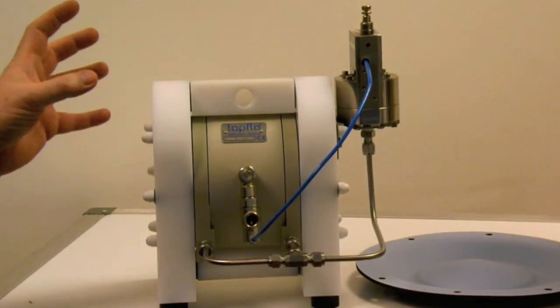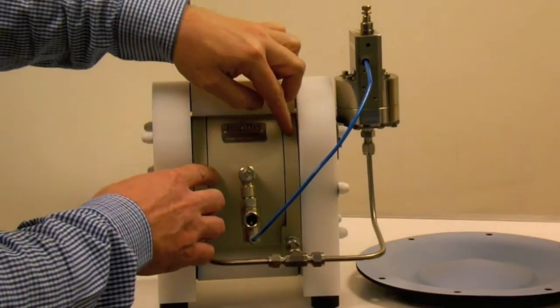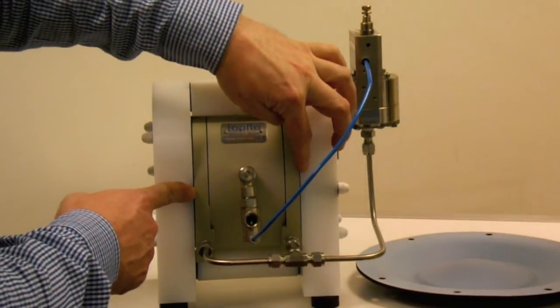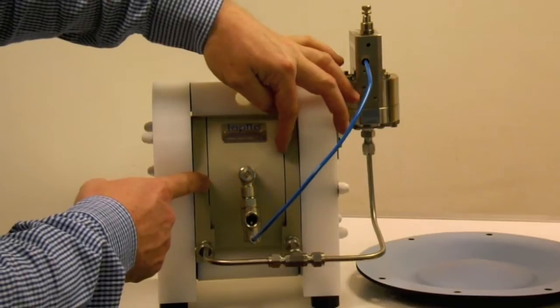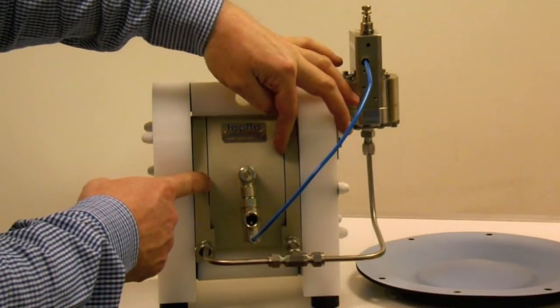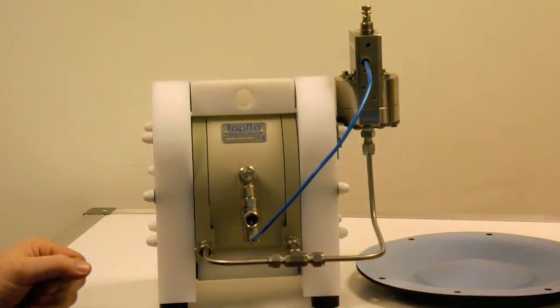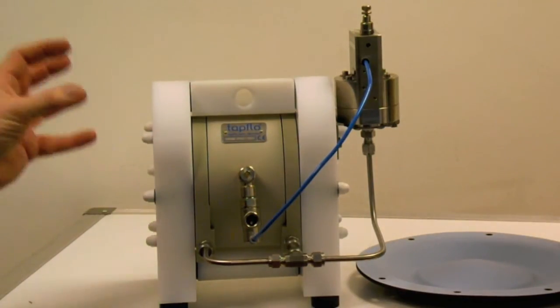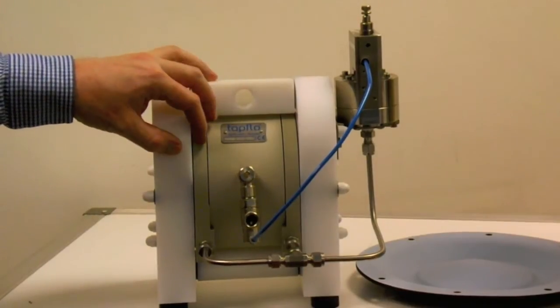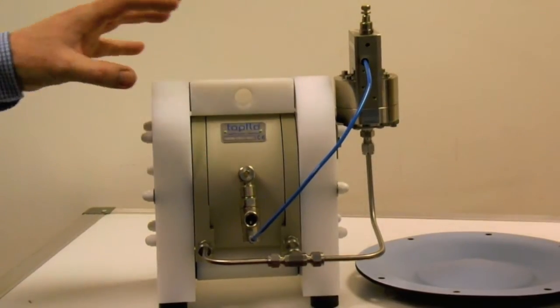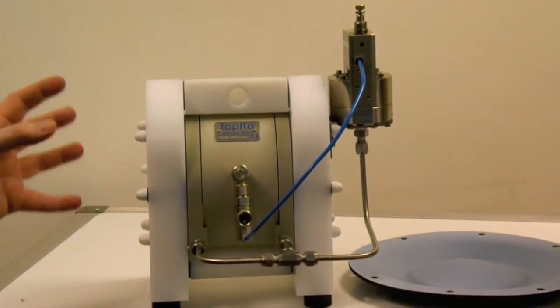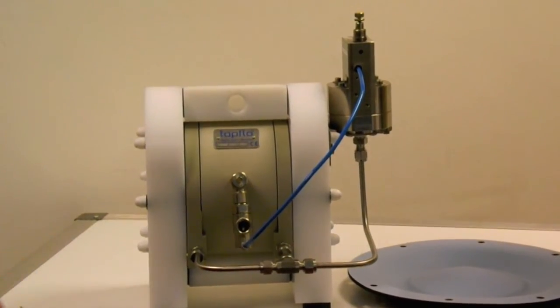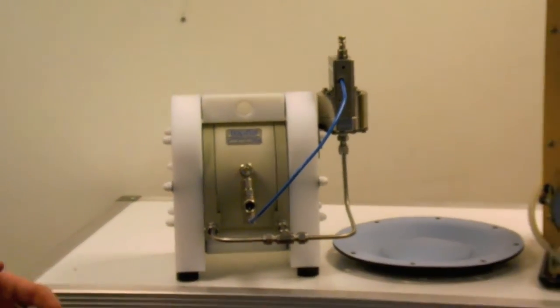With a barrier pump we have a second set of diaphragms. So we have our primary diaphragms on either side and then we have our backup diaphragms sitting in behind those with a spacer sleeve in between the two. Now what happens if we have a failure of a primary diaphragm, the product only gets as far as the backup diaphragm and then it is contained. Now the pump would normally continue to run in this situation until we had a failure of the backup diaphragm.